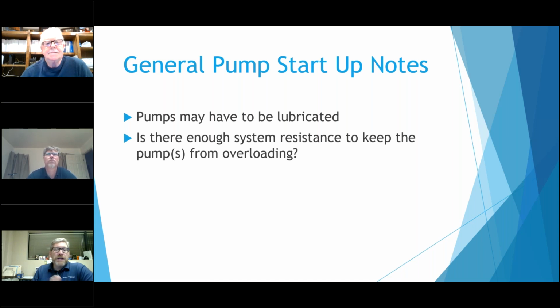This comment here about enough system resistance to keep the pumps from overloading is really from a new pump installation standpoint. Some of these you need to provide temporary heat, and the system's only partly on, it's just these units, not the whole system. So sometimes in these new systems, there's very little resistance. When you turn them up, the pump goes all the way to the right of the curve, off the curve, and now it's vibrating like crazy, making all kinds of noises.